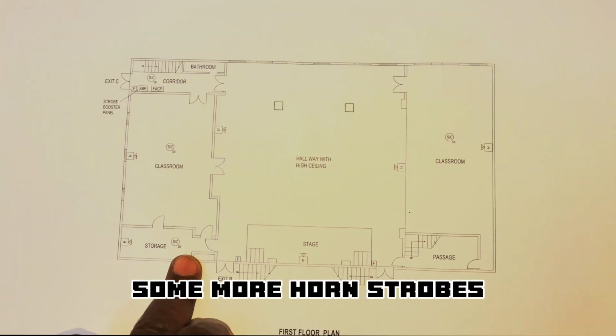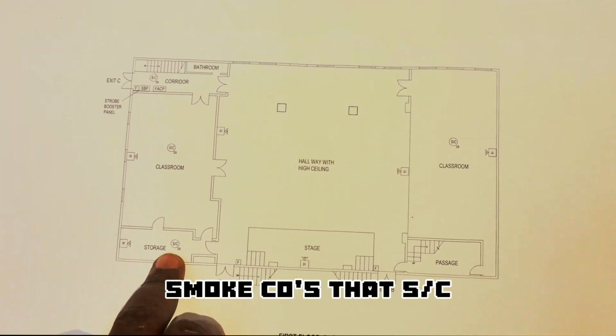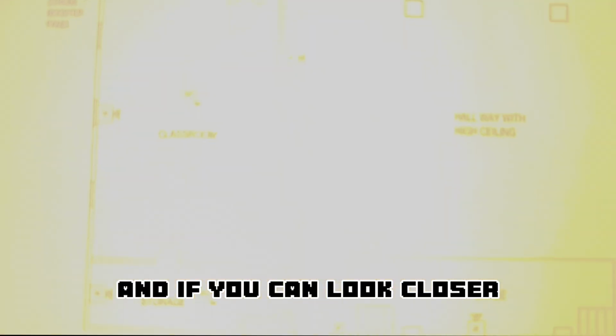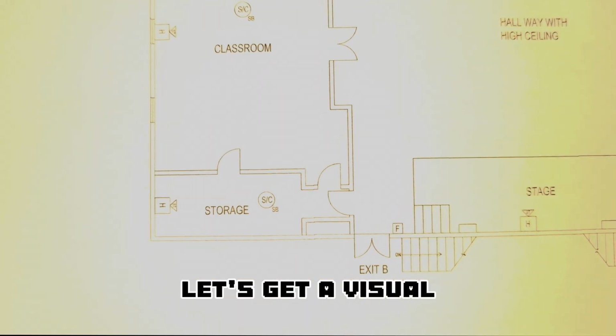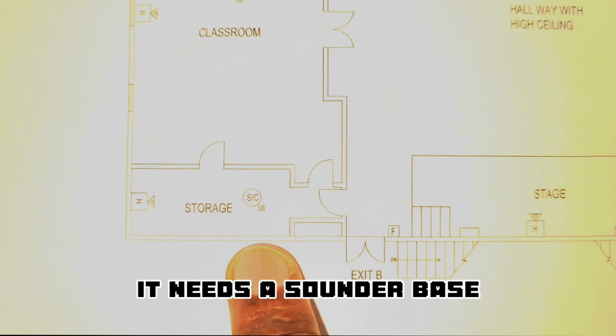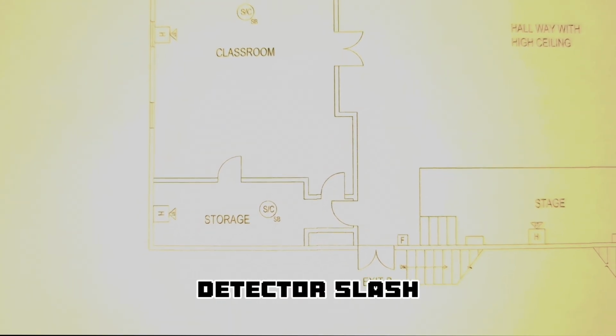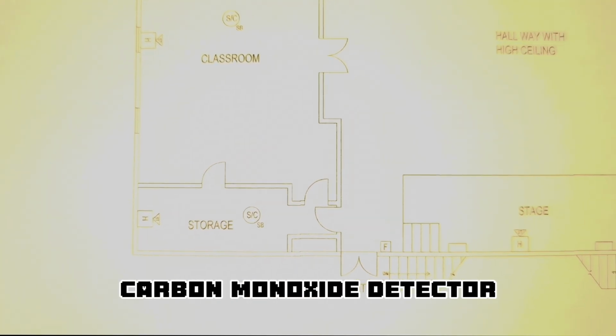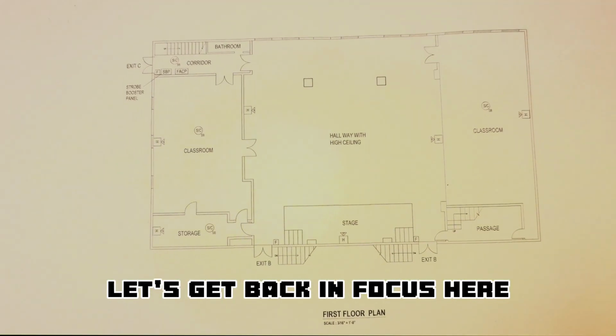Some more horn strobes, some more smoke COs. That SC says smoke CO, and if you look closer, let's get a visual. That SB means it needs a sounder base. So if you have a smoke detector / carbon monoxide detector, you also need a sounder base. Let's get back in focus.